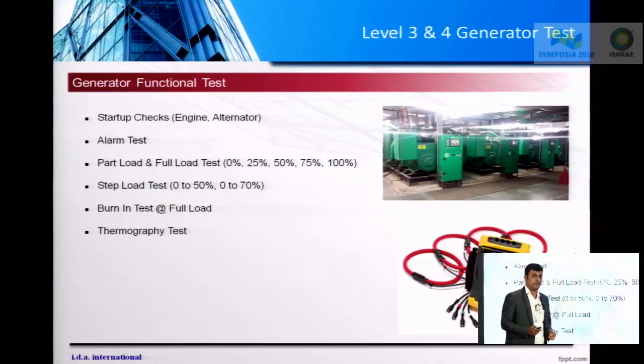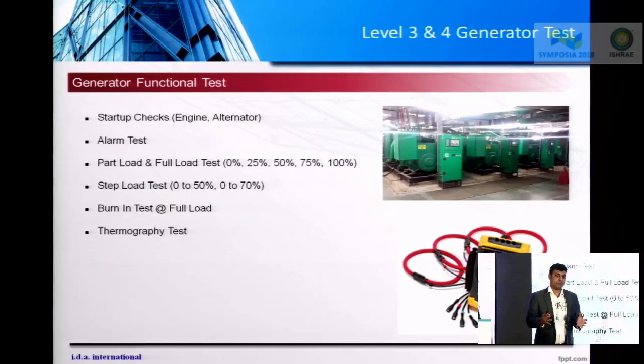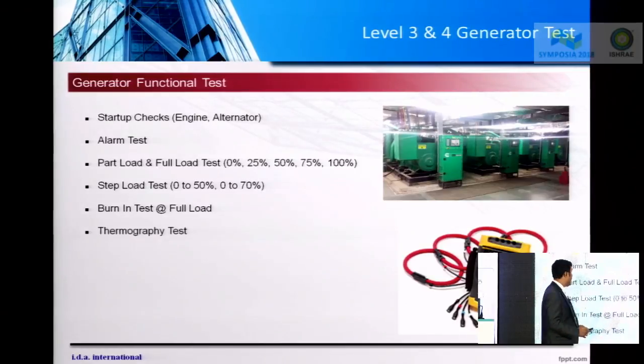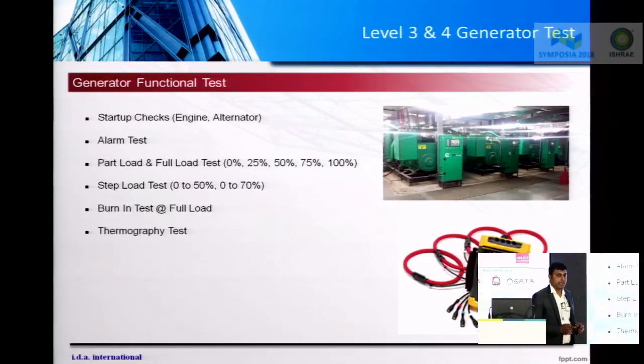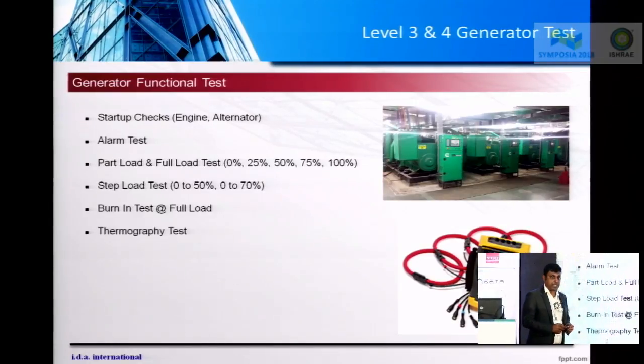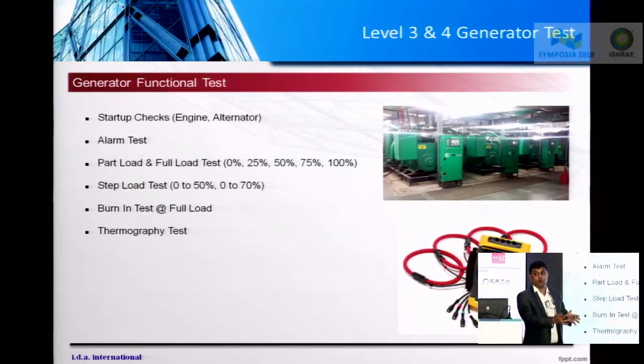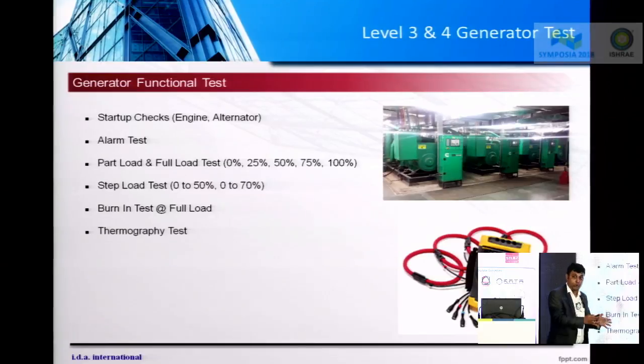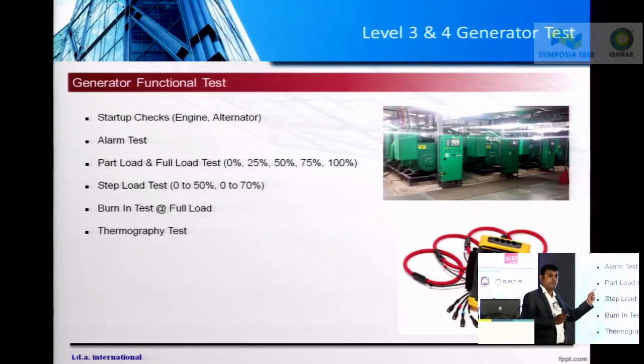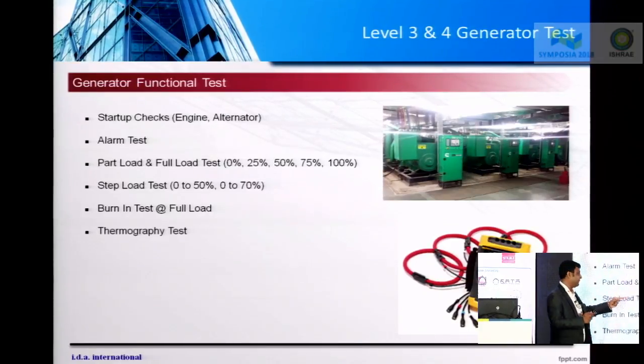Now let's take example of a generator. If I'm trying to verify the performance of a generator, I have to ensure that I'm doing the following checks. I'm verifying the startup checks for engine and alternator. I'm doing the alarm verification for generator. I'm verifying its performance during part load and full load condition. A step load test, which is a very critical step for a generator verification. Step load test from 0 to 50% or 0 to 70%. Then comes the burn-in test at full load condition and thermography.